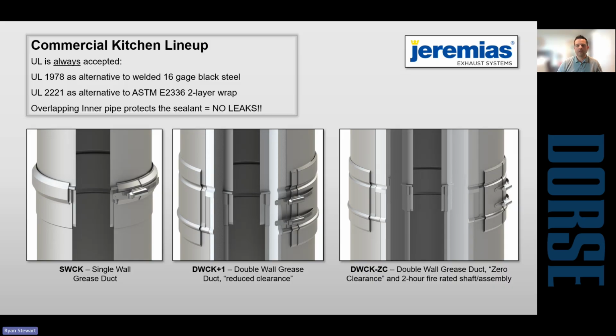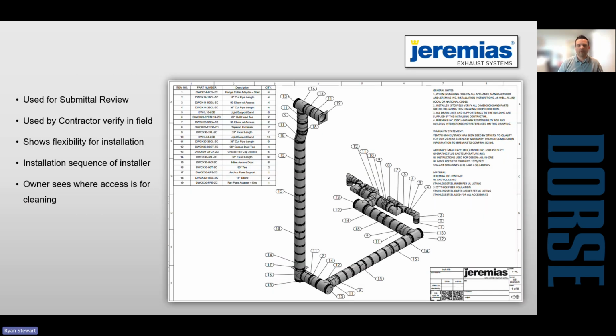The zero clearance is great, but from an installation standpoint, the more insulation you add to the product, the heavier it is, and it's just more challenging for people to install. This is an example of what a shop drawing would look like. You can see that they have clean outs, all kinds of fittings to configure it. They have cut pieces to allow flexibility for the installers in the field.